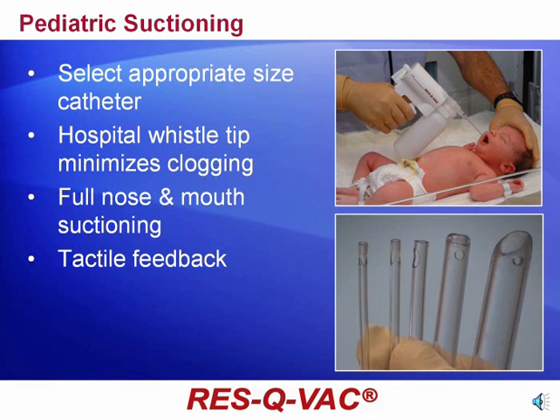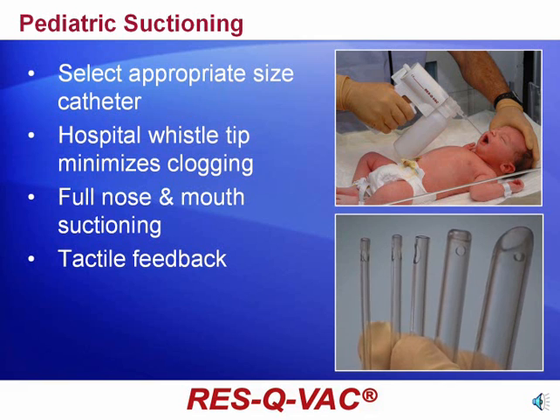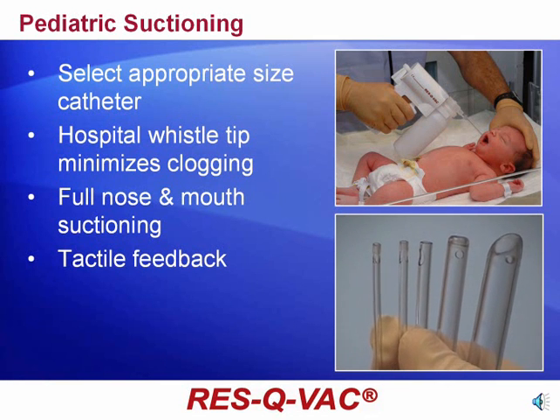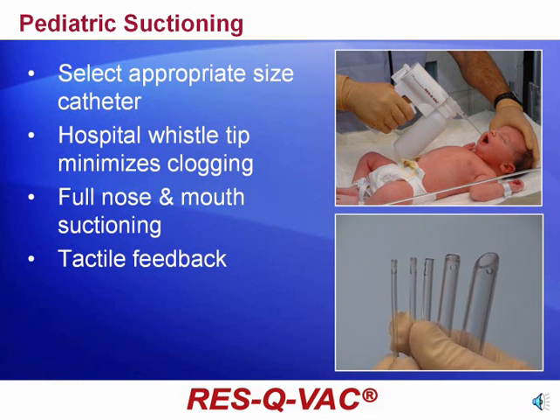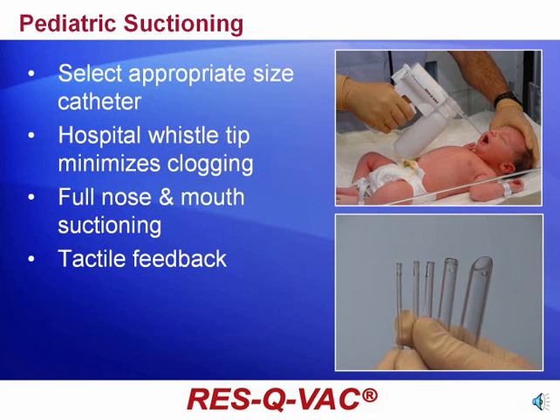To use the RES-Q-VAC on pediatrics, select the appropriate size catheter for infant or child. Again, all catheters are whistle-tipped and will not block off during suctioning. Place the catheter below fluid level and squeeze the handle while withdrawing the catheter. Squeeze the handle as necessary to reach the suction level required. You have full tactile feedback, which means you will be able to feel what suction level you are at by applying force to the pump handle.